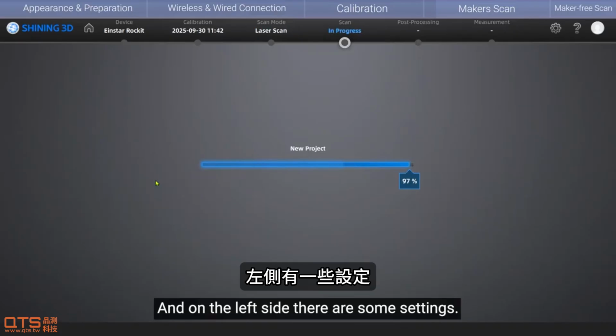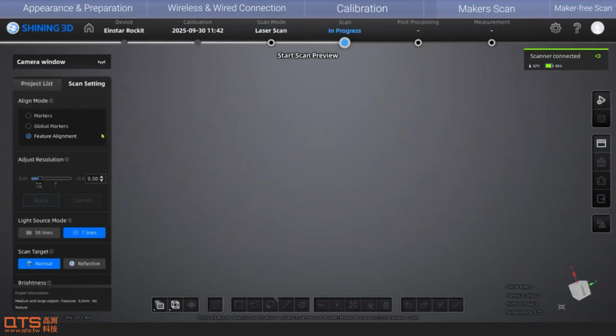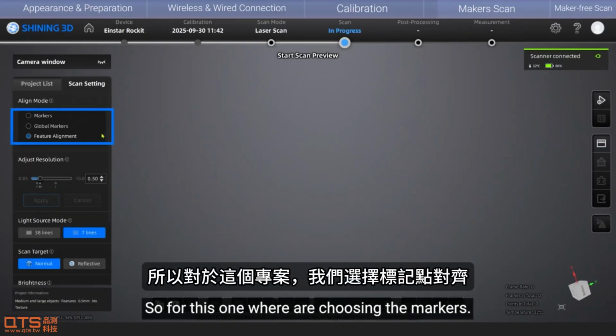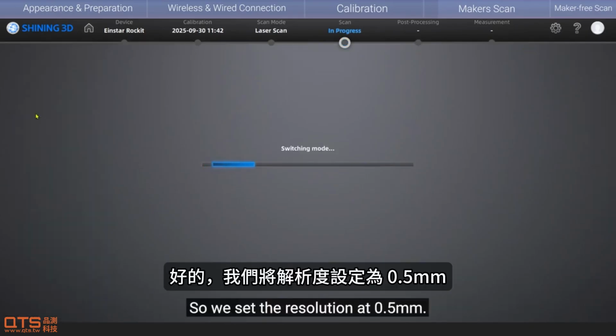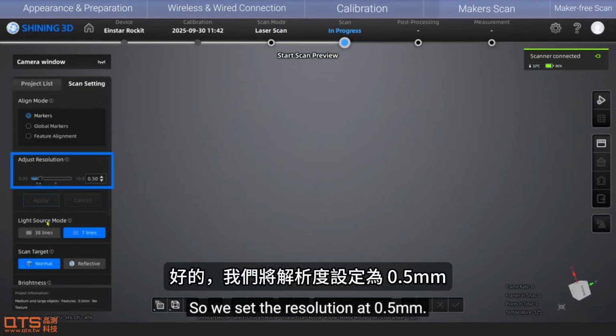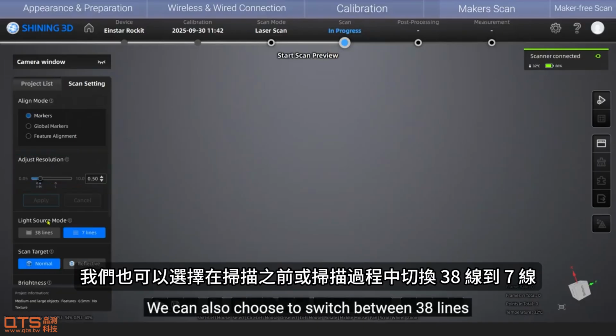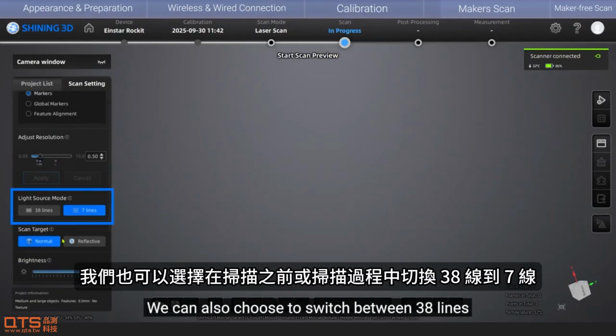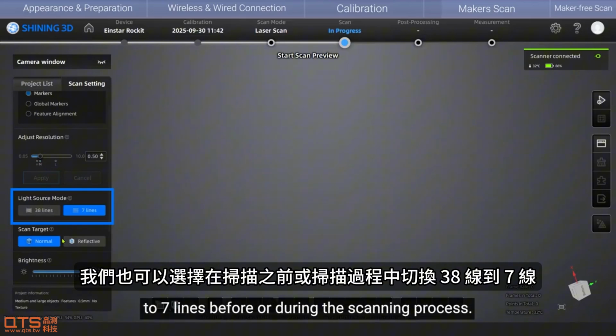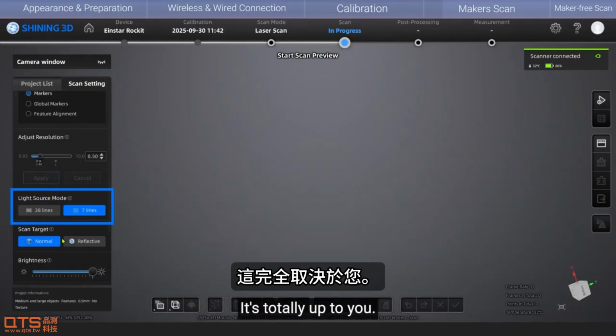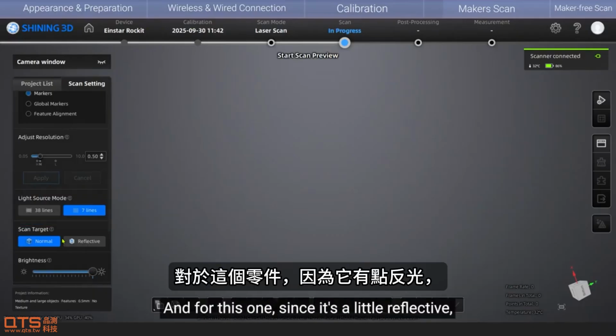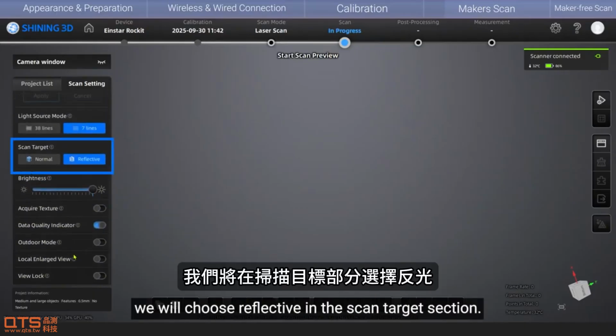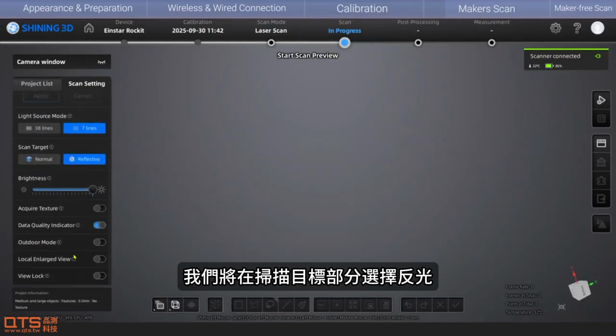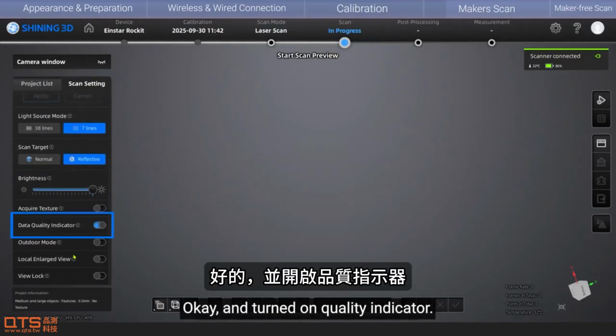And on the left side, there are some settings. So for this one, we are choosing the markers. Okay, so we set the resolution at 0.5 millimeter. We can also choose to switch between 38 lines to 7 lines before or during the scanning process. It's totally up to you. And for this one, since it's a little reflective, we will choose reflective in the scan target section. Okay, and turn on quality indicator.